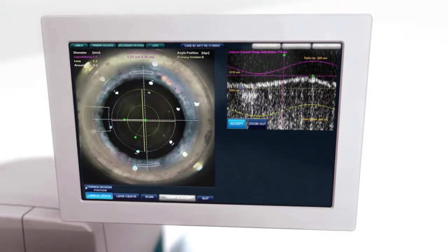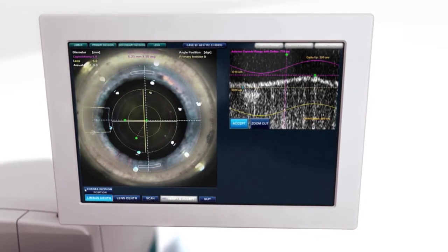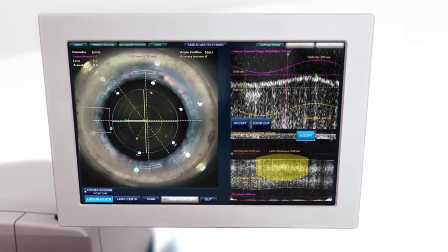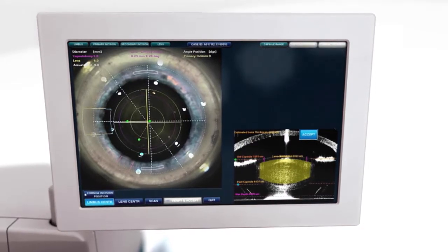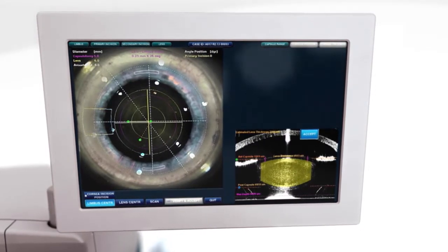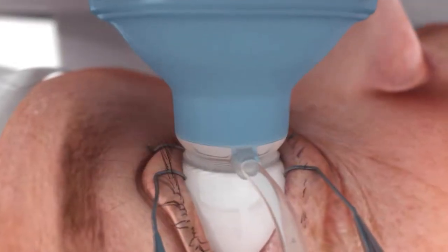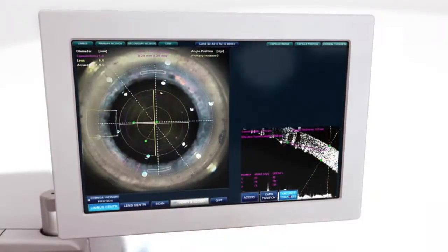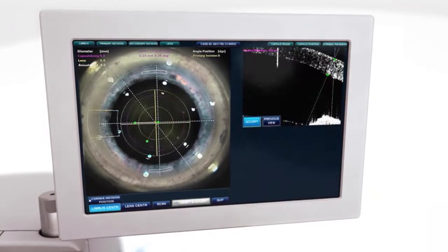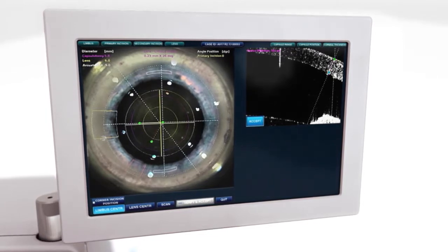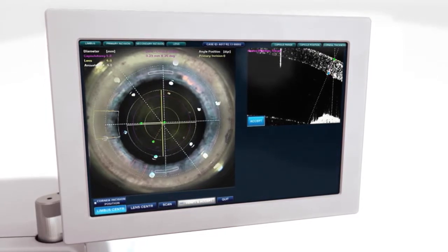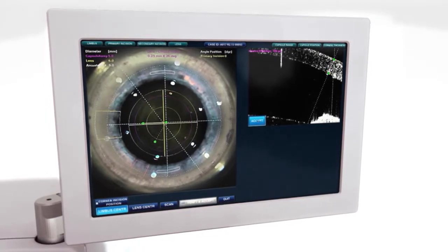A wide range of laser settings allow for surgeon customized size, shape and location of each incision, lens fragmentation and the depth of cuts. Trapezoidal primary and secondary incisions may also be selected for optimized wound architecture and ease of IOL delivery.